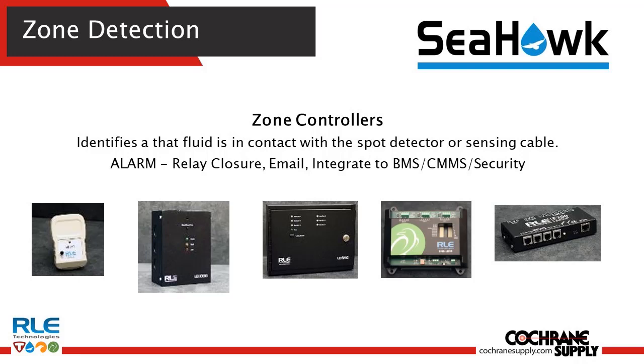It also has 8 digital inputs, has the capability to bring in some IP connections, could be cameras that you may want to bring in to create a single pane of view. But then the alarm capabilities could be Modbus IP. Again, it's got a user interface and software built into it, so the ease of setup is mind-blowing how simple it is, quite honestly. And for all of the different applications above and beyond the simple leak detection, certainly has a platform and fit inside of building automation.